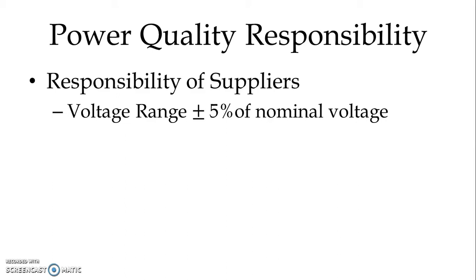The very important is voltage range. We know that plus or minus 5% of the nominal voltage is allowed because most electrical equipment is designed to operate within a voltage of plus or minus 5% of nominal voltage with marginal decrease in performance. The overall effect of voltage excursion outside the nominals is not that significant unless the voltage approaches the limit of plus or minus 10% of the nominal.